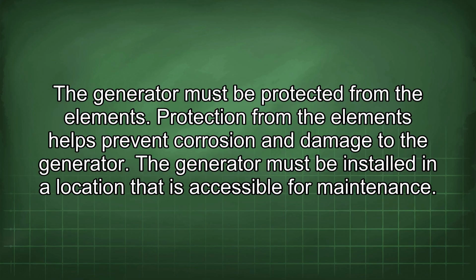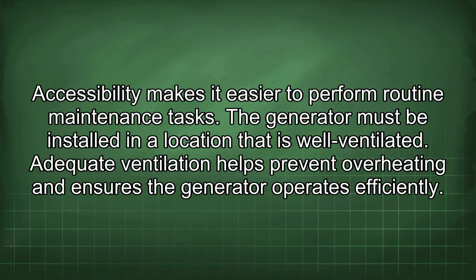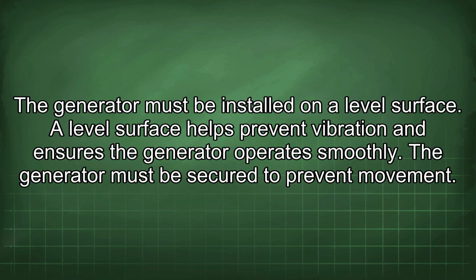The generator must be installed in a location that is accessible for maintenance. Accessibility makes it easier to perform routine maintenance tasks. The generator must be installed in a location that is well ventilated. Adequate ventilation helps prevent overheating and ensures the generator operates efficiently. The generator must be installed on a level surface. A level surface helps prevent vibration and ensures the generator operates smoothly.